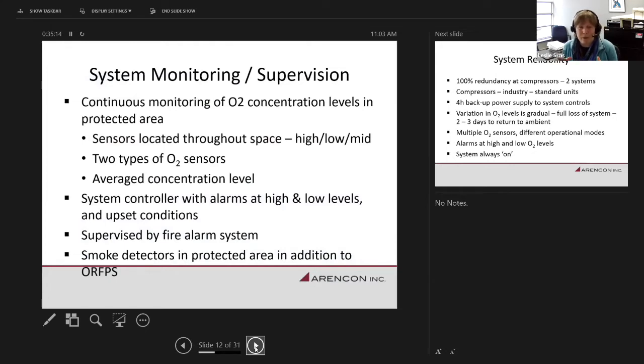So you're always going to be continuously monitoring the oxygen concentration levels in the protected area. The sensors are high, low, mid, there's the blend, there's the calibration of the sensors, both when they're installed and on an annual basis. So these sensors are pulling back information, saying more nitrogen, less nitrogen, giving warnings to people outside the space, inside the space, about if there's variances beyond the normal operating threshold. There can be supervision through the fire alarm system for what we'd say are abnormal, like the extreme conditions. The smoke detectors, you can also supervise it through the building automation system.